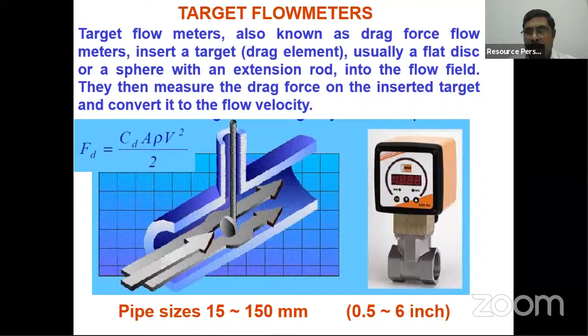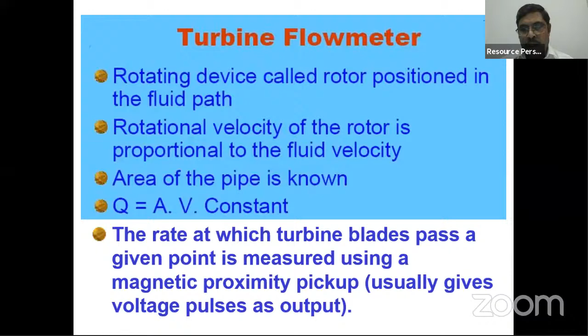Okay. The turbine type flow meter is a very, very simple type of flow meter. It's a first order type flow meter. Here there will be turbine plates which will be kept in the flow path. When the flow takes place, the turbine will rotate, and by observing the rotation of the turbine, you can measure the flow rate. Here again the response is very fast and very simple, but the only thing is that since we need to install the turbine inside the pipe, it will offer a pressure drop. That of course you have to consider.